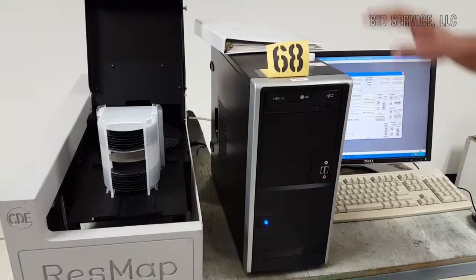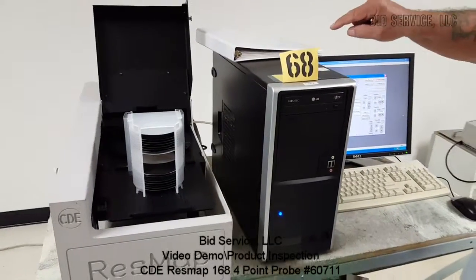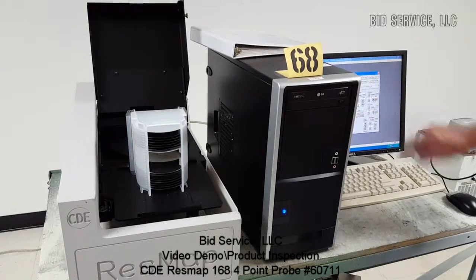To calibrate the unit, we used a resistance pack in place of the probe and then did the calibration procedure according to the manual.